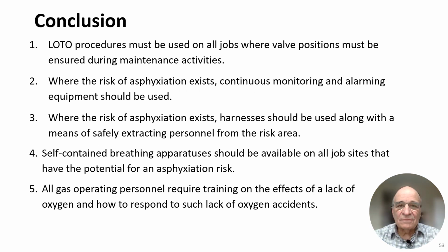In conclusion, LOTO, that's lockout tagout procedures, must be used on all jobs where valve positions must be ensured during maintenance activities. Where the risk of asphyxiation exists, continuous monitoring equipment and alarming equipment should be used. Where the risk of asphyxiation exists, harnesses should be used along with a means of extracting personnel from a high-risk area. Self-contained breathing apparatus should be available on all jobs that have the potential for asphyxiation risk. All gas operating personnel require training on the effects of a lack of oxygen and how to respond to such accidents.